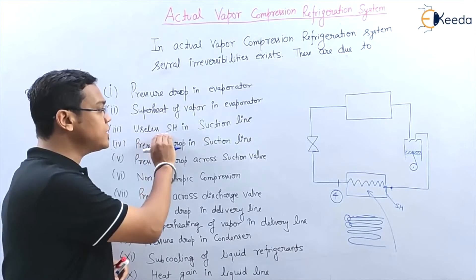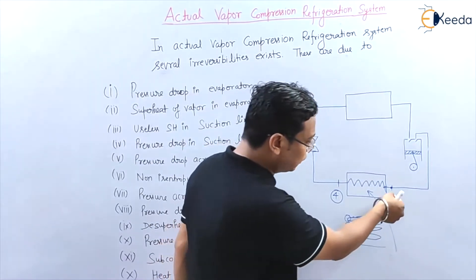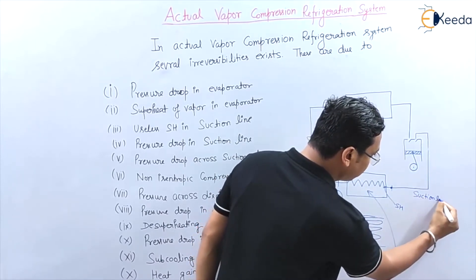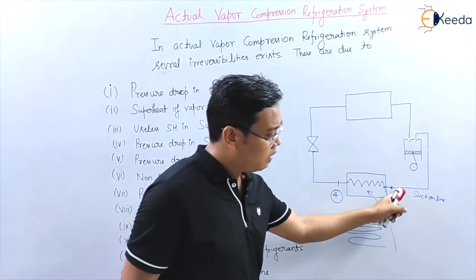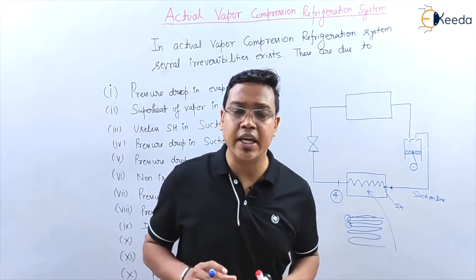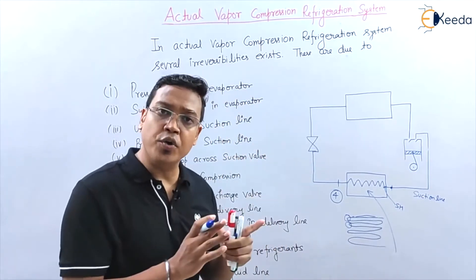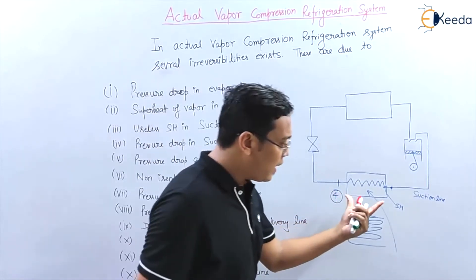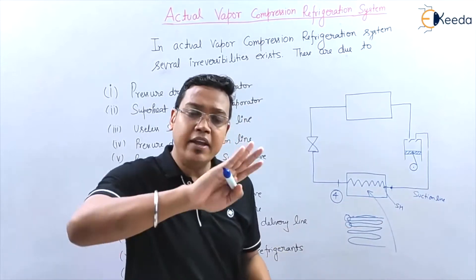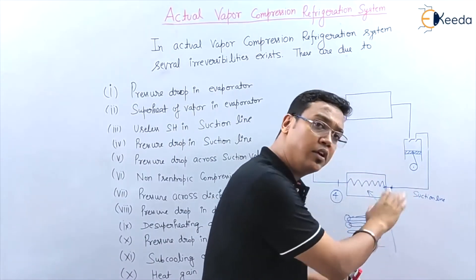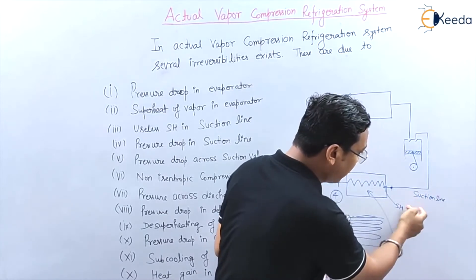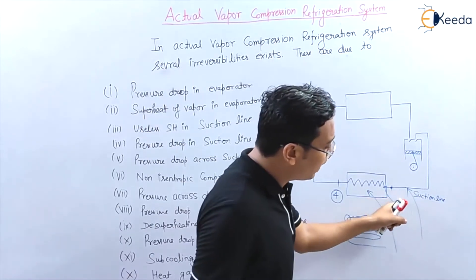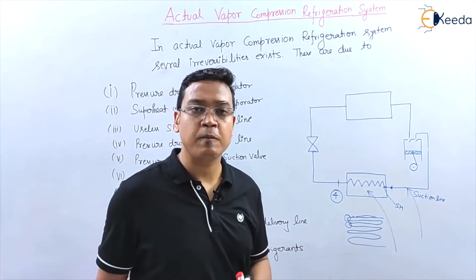The third point is useless superheating in the suction line. The suction line — as seen in window AC or split AC — is located inside the room. Because this suction line is inside the room, it also absorbs heat from the room, causing extra superheating of the refrigerant in the suction line.